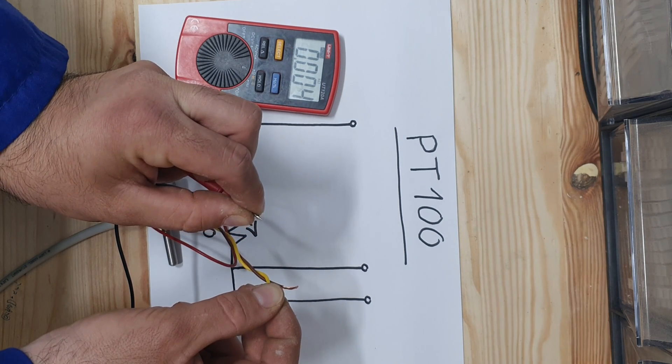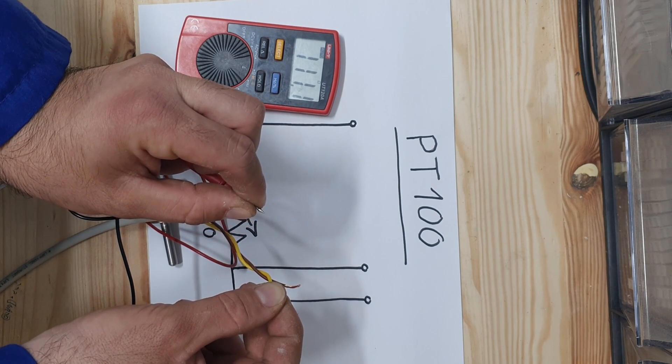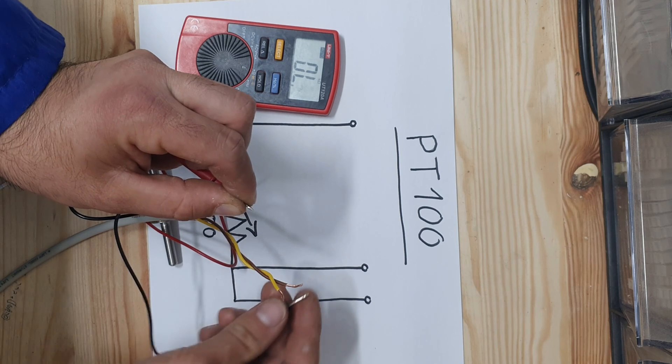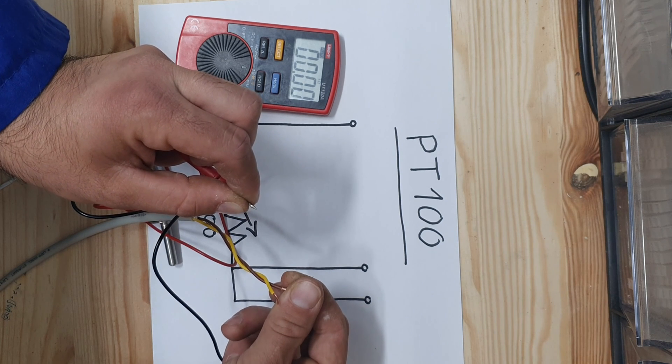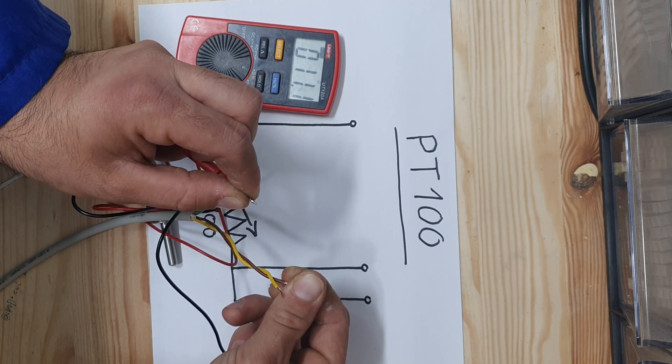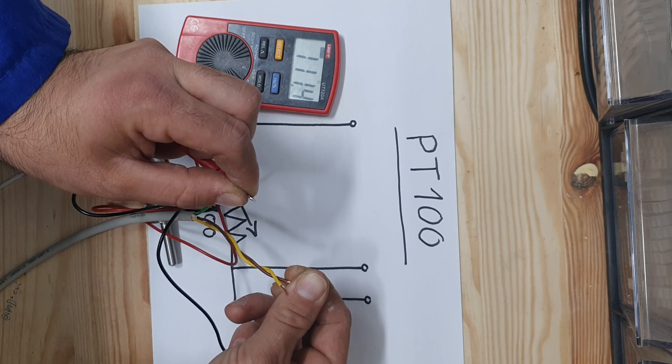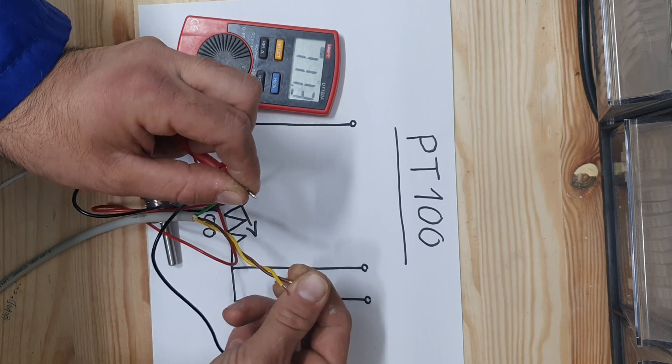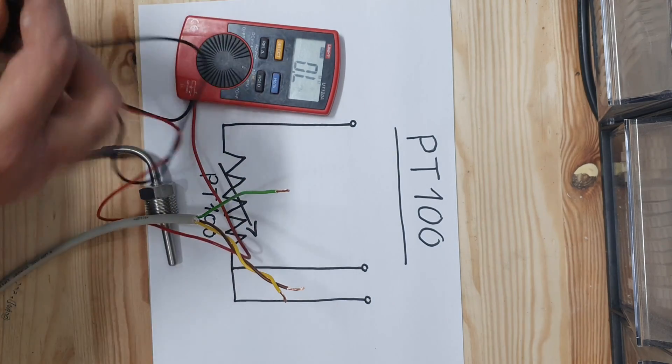When you connect PT100 to a controller or to a transmitter, the device calculates the resistance of the wires and ignores them while measuring the PT100. That way, you have more accurate readings.